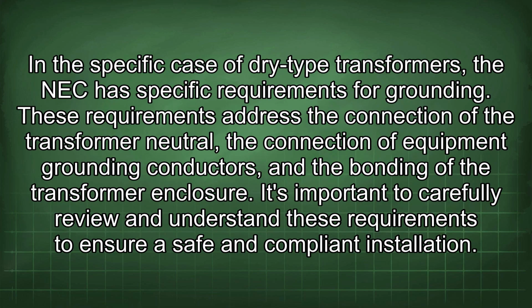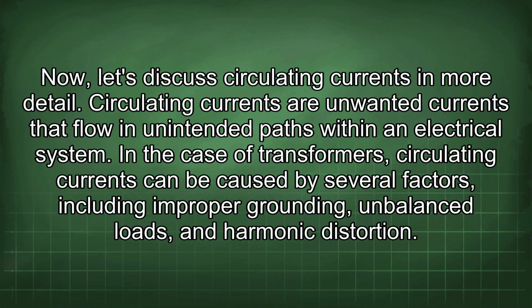In the specific case of dry-type transformers, the NEC has specific requirements for grounding. These requirements address the connection of the transformer neutral, the connection of equipment grounding conductors, and the bonding of the transformer enclosure. It's important to carefully review and understand these requirements to ensure a safe and compliant installation. Now let's discuss circulating currents in more detail. Circulating currents are unwanted currents that flow in unintended paths within an electrical system. In the case of transformers, circulating currents can be caused by several factors, including improper grounding, unbalanced loads, and harmonic distortion.